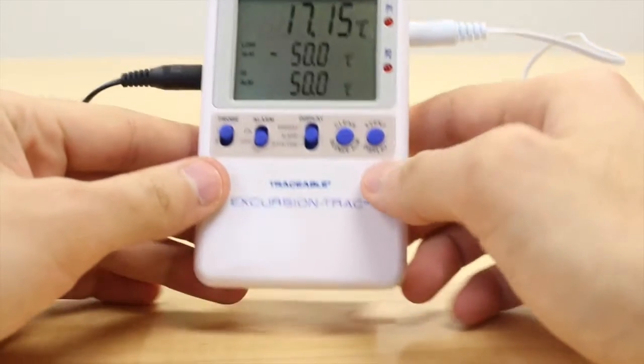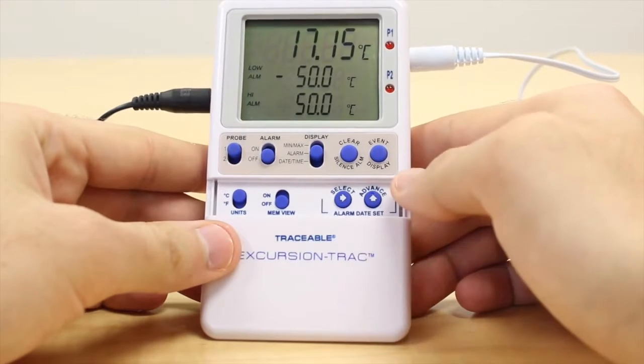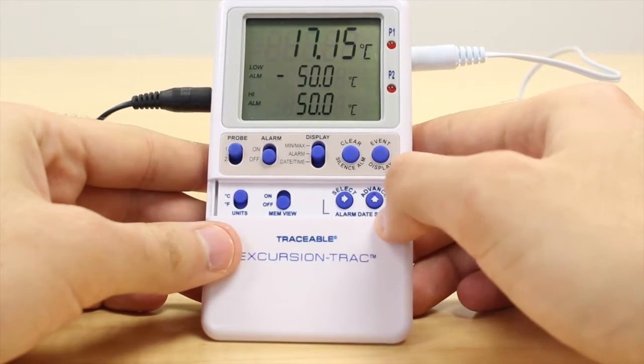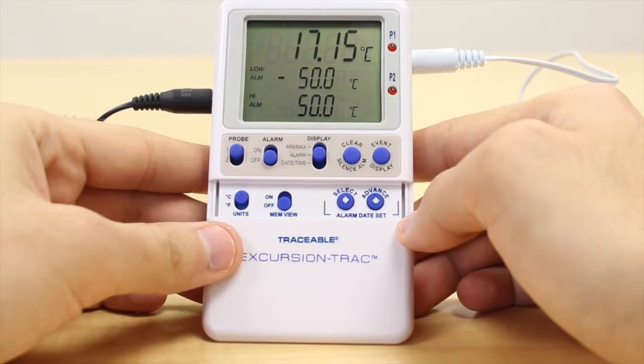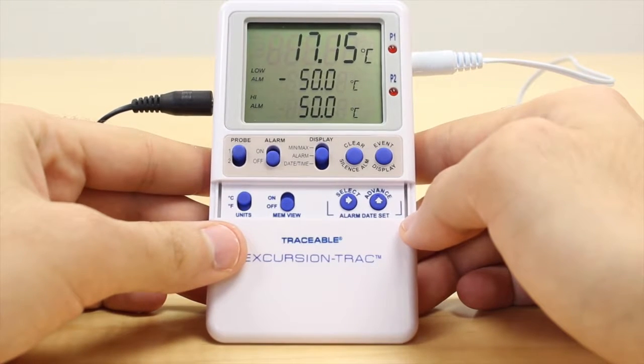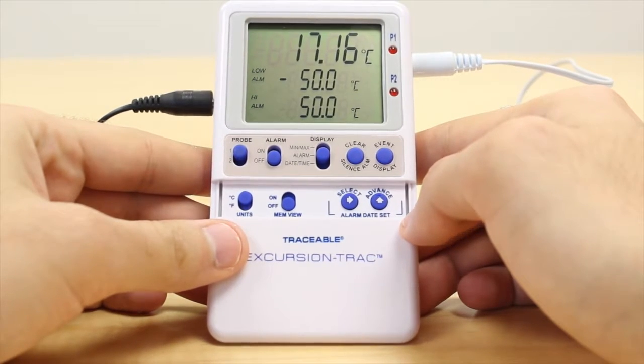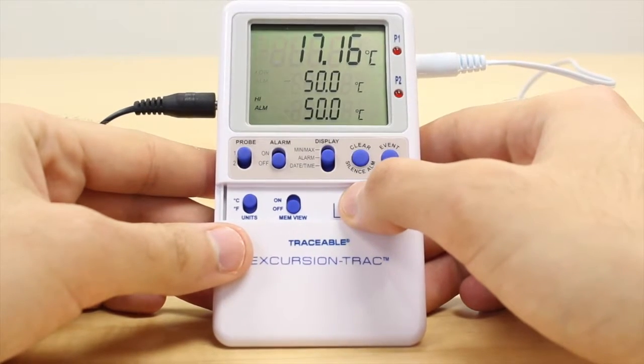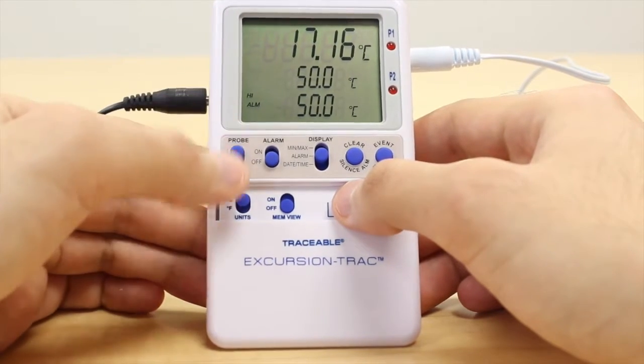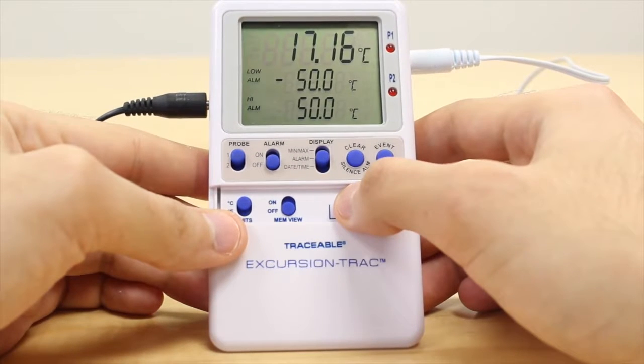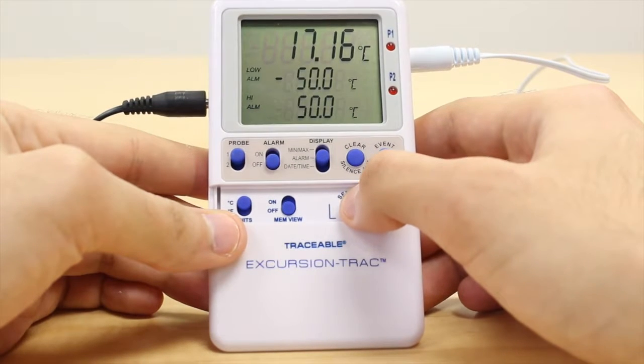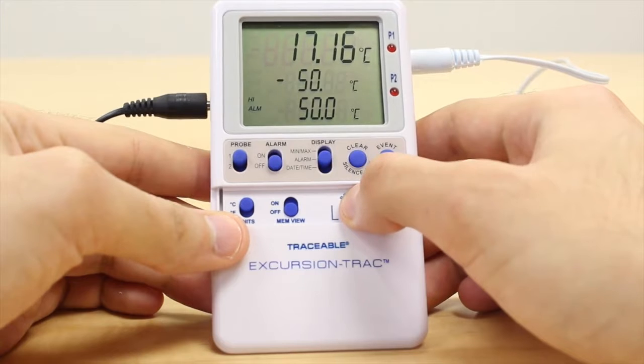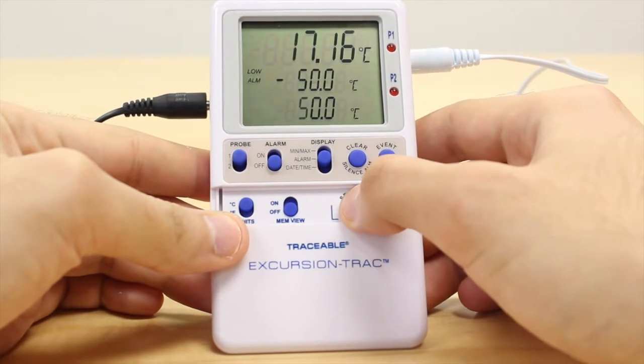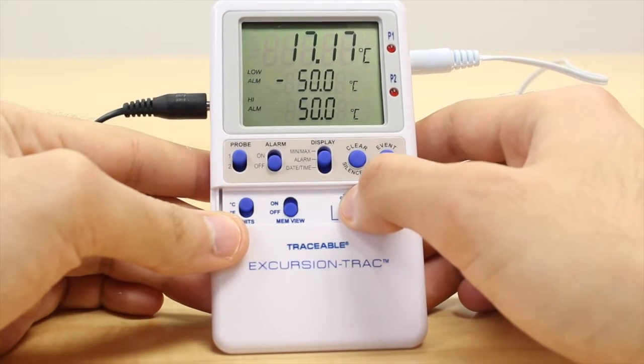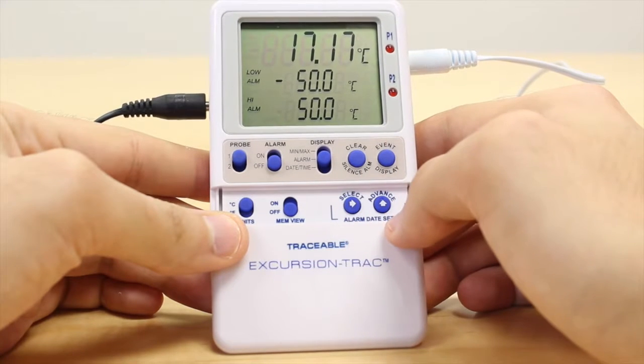Slide open your Excursion-Trac and this will reveal the 2 buttons you will use for this lesson, Select and Advance. The Select button will move between each individual digit and the Advance button will change each value. First, let me show you how the Select button works. The first press of the Select button takes me to the negative symbol on the low alarm row. Another press takes me to the next digit. Another press takes me to the next digit. And then another press takes me to the next digit in that row, and so on and so on. Once you reach the end or don't touch any buttons for 15 seconds, you'll exit alarm setting mode.